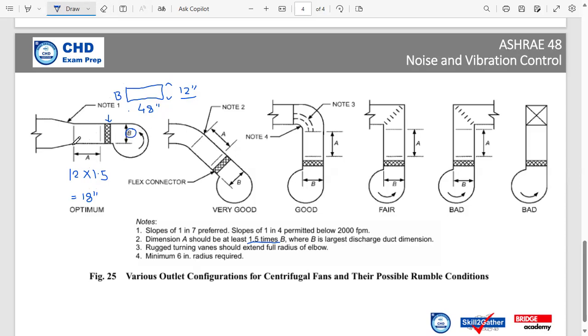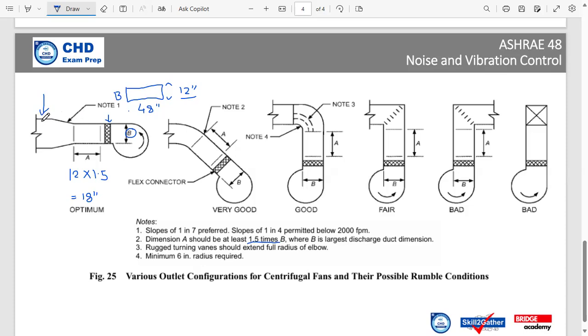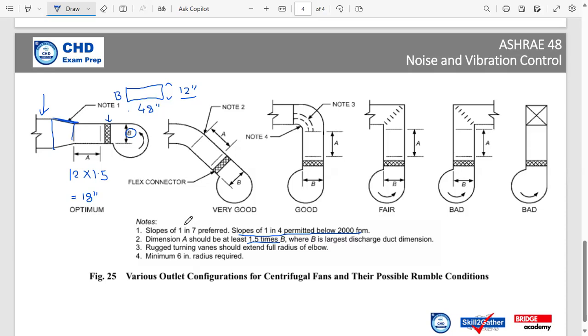After that, we are going to meet the regular duct design. We have the duct that we do calculation as per our requirement. Now we have to connect this duct with this fan system. In this case, we are going to need a slope or neck in here. ASHRAE recommends a slope of 1 by 4 if the velocity is below 2000 feet per minute. However, it is always preferred slope 1 by 7. That is actually the preferred one.